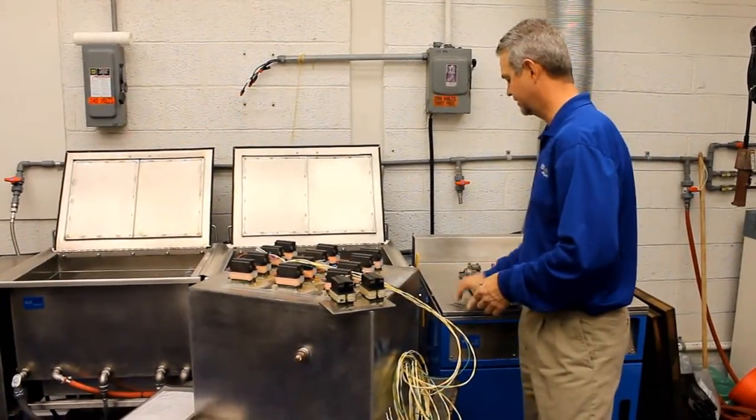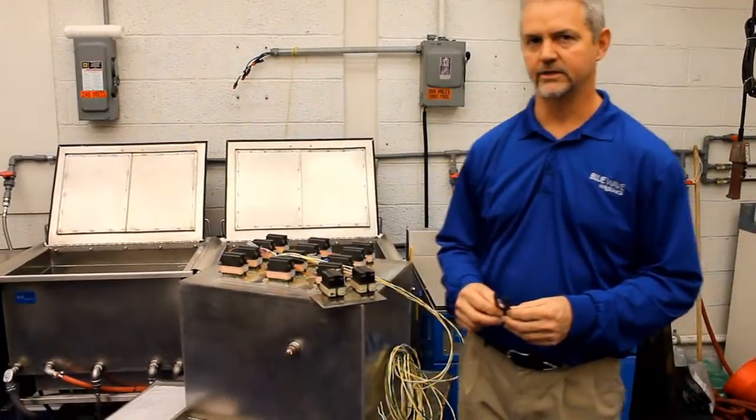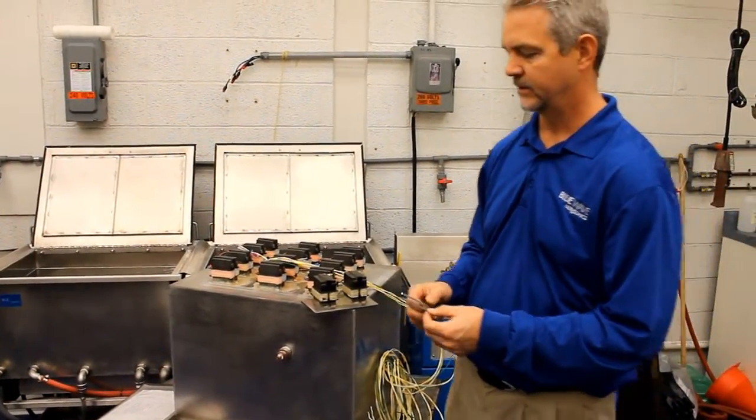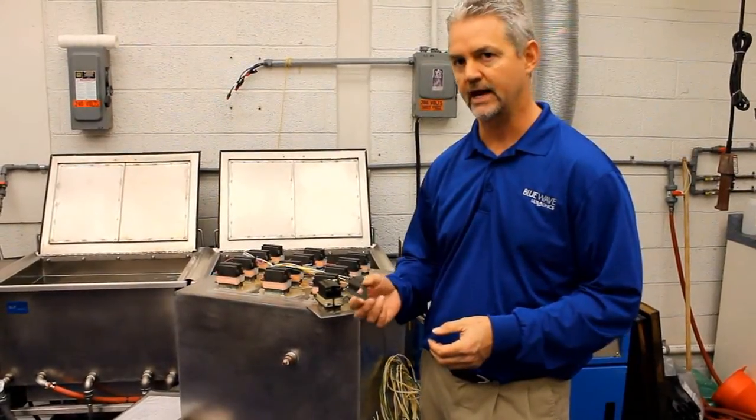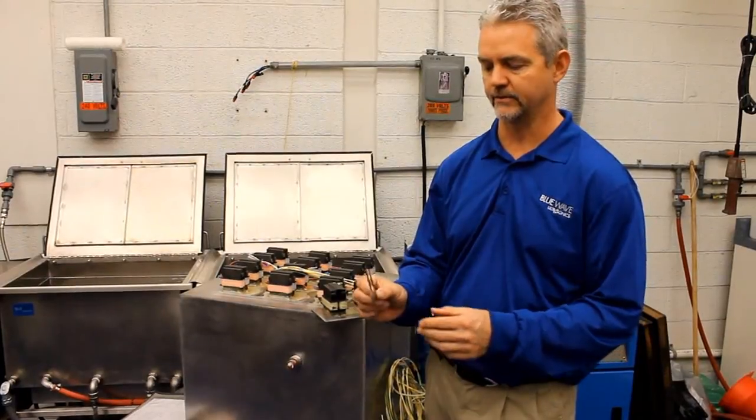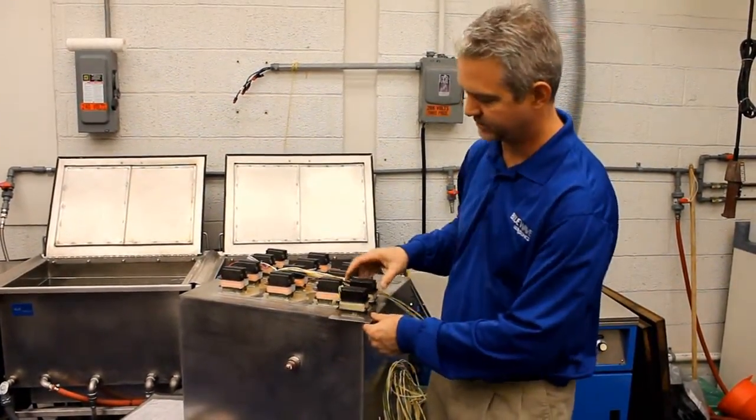Blue Wave manufactures a completely different type of ultrasonic system. We make what's called a zero-spaced, silver-brazed, magnetostrictive transducer. This transducer consists of pure nickel alloy. We start out with U-shaped laminations, pure nickel, and they're formed into a stack.